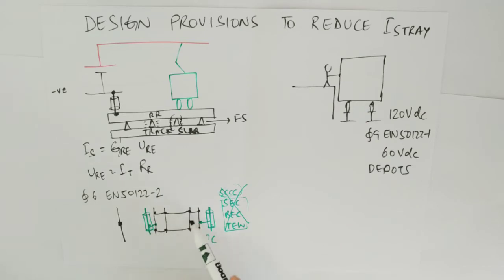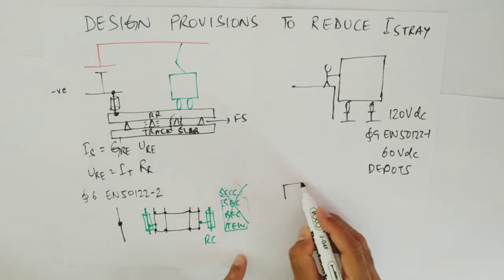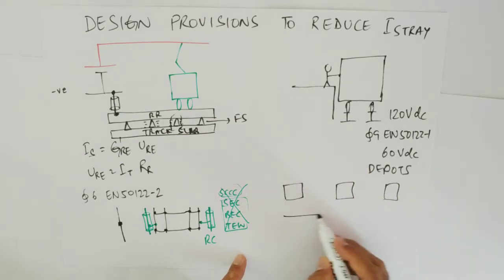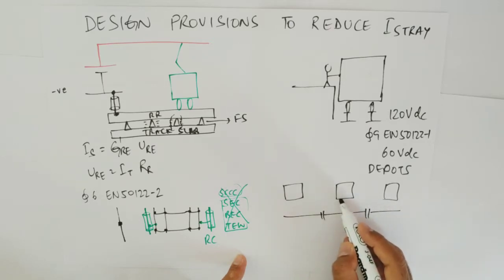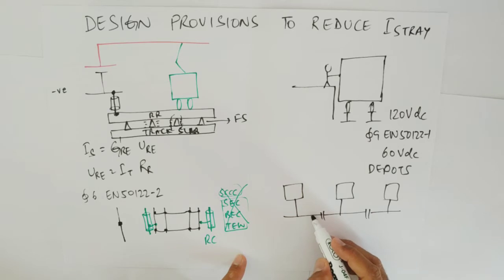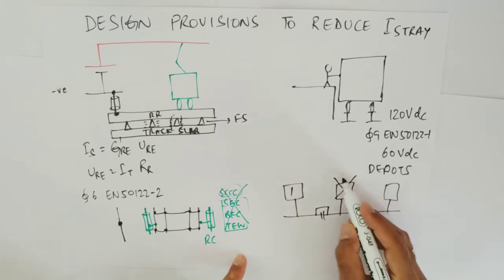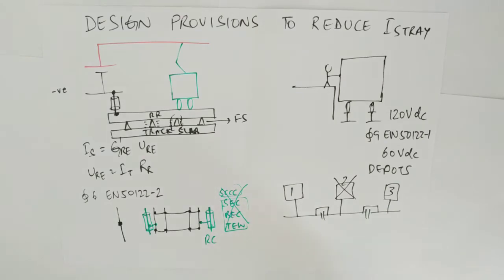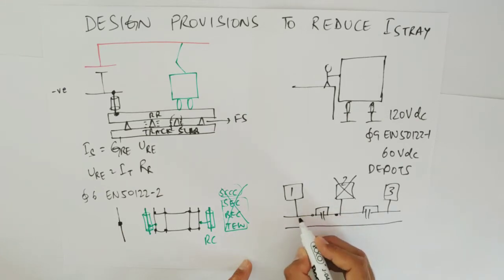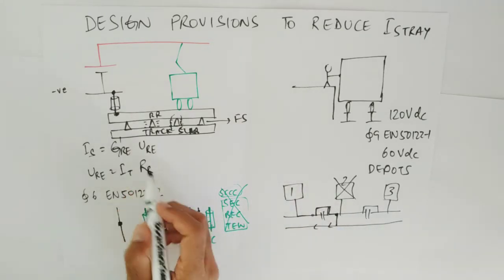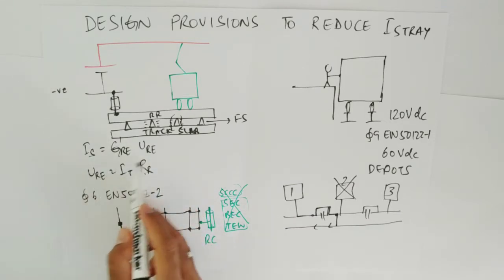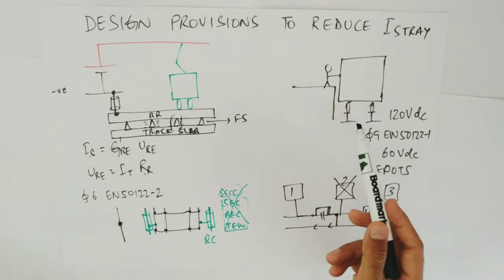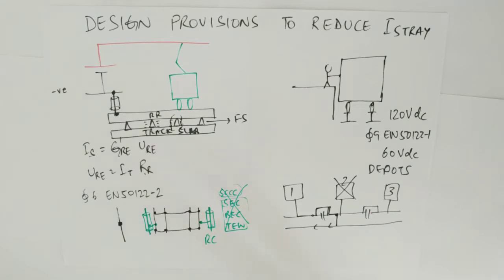In the N-1 case, suppose there are three traction substations feeding separate sections. If one substation fails, the adjacent ones extend their supply. The running rails over a longer section carry the traction current, increasing the rail length and therefore the resistance. Once resistance increases, the rail potential increases, and if it goes above 120 volts DC the person can get an electric shock.